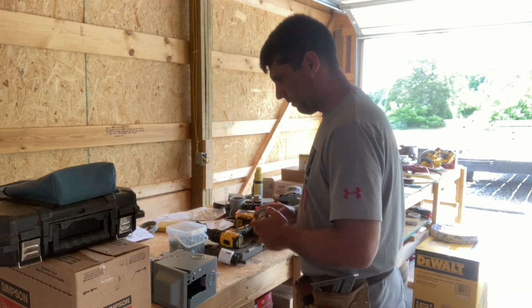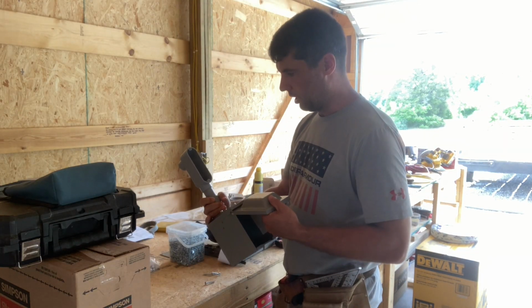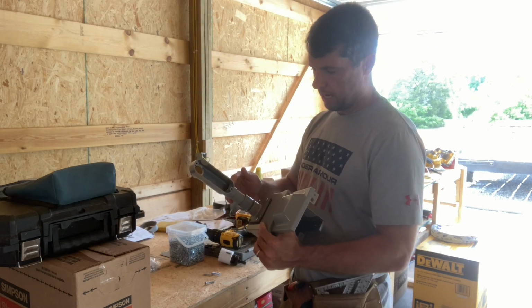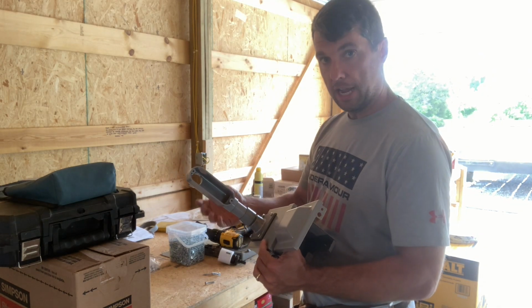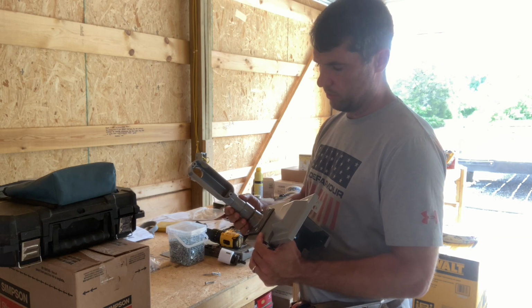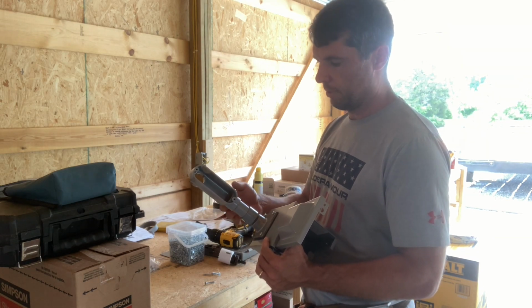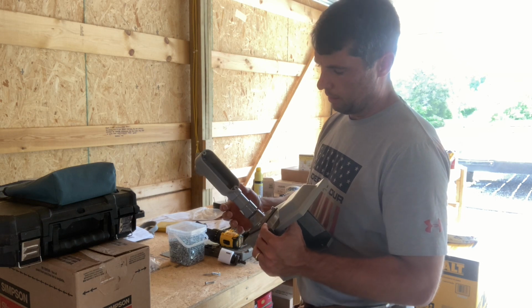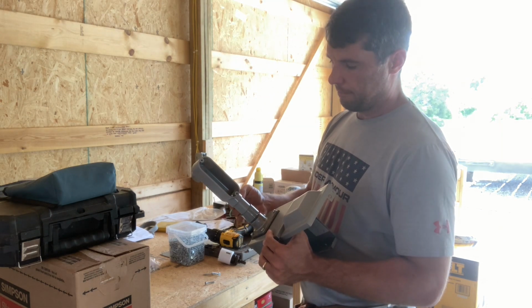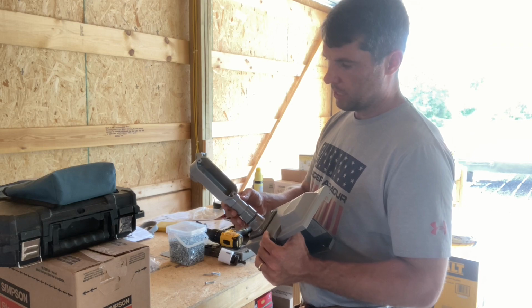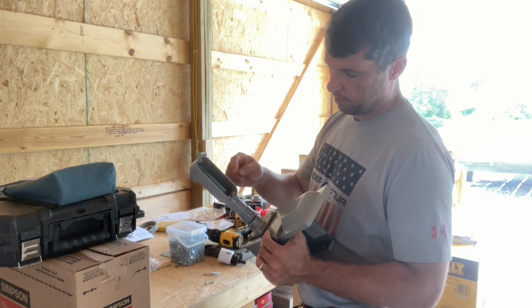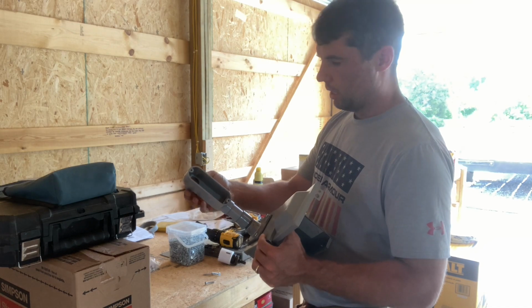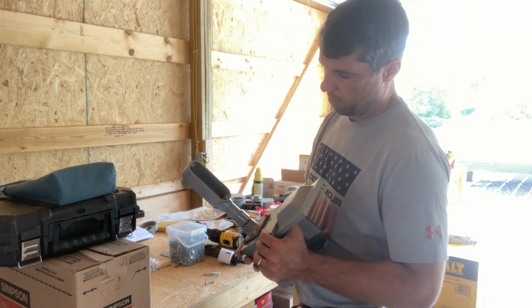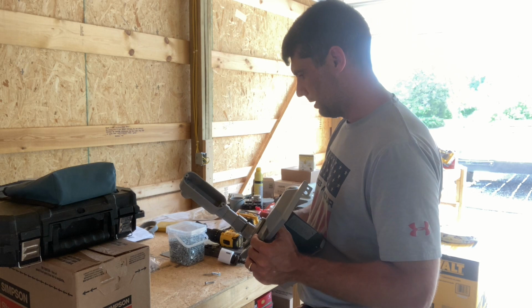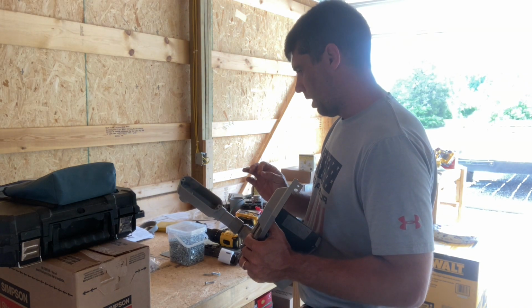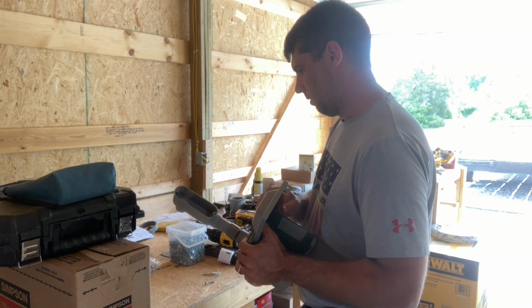All right, I think I have this figured out. This is my exterior plug. I have 1-inch conduit coming down - again, you have to read code to know what size conduit to use based on the size and number of conductors going through it. So this is 1 inch. I'm going to have 3 number 6 wire conductors run through this to the plug, and it's going to go directly into the breaker box from this box. I have that planned out and feel comfortable with it.